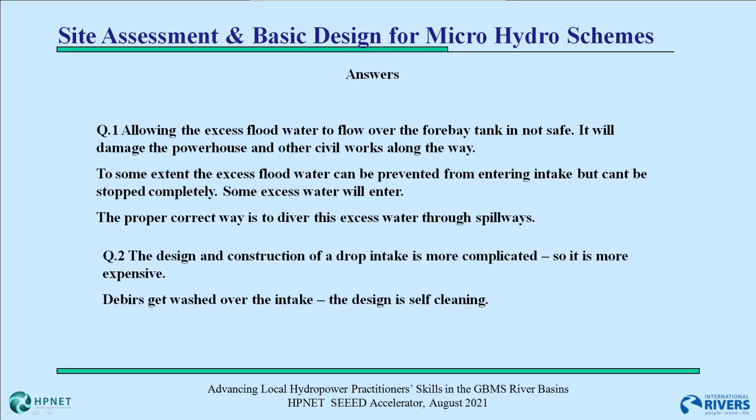The second question, the drop intake is more complicated, so it is very difficult to build and thus it is more expensive. It is not cheaper. So that's the wrong answer. But the design is self-cleaning. It's a correct answer. Debris get washed over the intake without any external work. By the very design of the intake, the debris cannot enter into the trench. It gets pushed over by the flowing water. So it is self-cleaning. That is a major advantage of drop intakes.